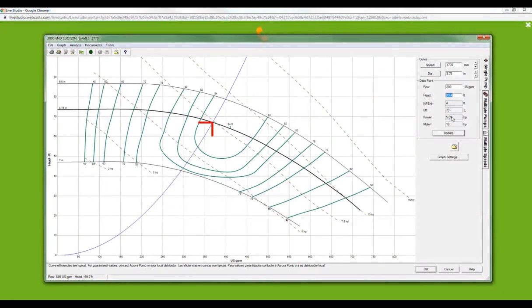And what happened to our power? Our power went to 5 horsepower. At 368, our power was 7 horsepower. So we saved a little bit. We throttled the pump, we closed the valve, and we saved a little bit of horsepower, from 7.3 down to 5.5 horsepower. As an alternate to that, what would it do if we reduced the rotating speed?